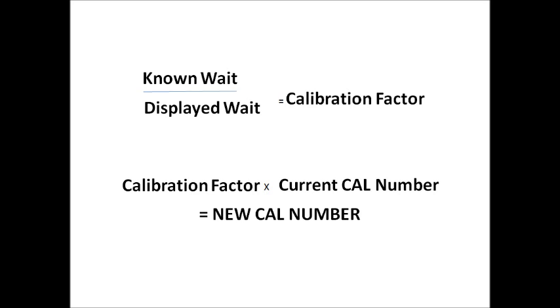A calibration factor, normally a decimal number, take that times your current calibration number programmed in the indicator, which will then equal your new calibration number.